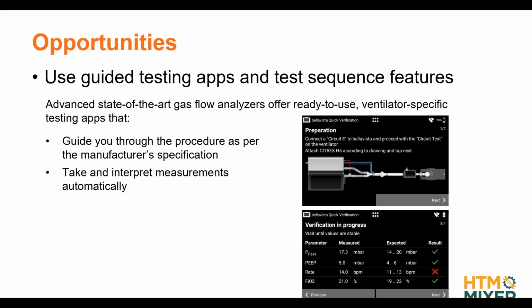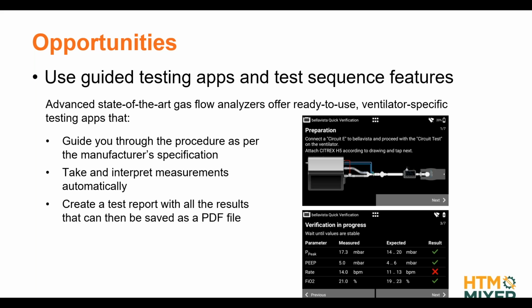And then they can take the measurements and interpret them automatically, because they know, okay, for this ventilator, these are the values, and they can calculate the expected ranges because the measurement is already there on the device, right? Sometimes you need to key in something that you read on the ventilator, and then it's doing the math, like the Excel spreadsheet you mentioned, and it can give you pass-fail results right there on the screen, okay? And then they can also store all these results and put them into a report at the end that you can then download from the device as a PDF file.